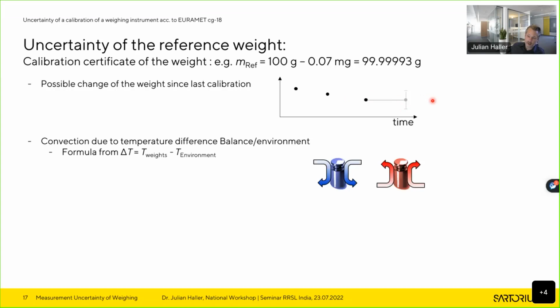And you have to take into account if the weights that you use are not perfectly acclimatized. If you have a temperature difference between the weights and the surroundings, you might get convection. If the weight is colder than the surroundings, then air that approaches the weight will cool down, go downwards and, by friction, cause a force on the weight. So a colder weight will appear heavier, while a warmer weight will appear lighter. And you have to take that into account. This can only be done by a reliable estimation of the temperature of the weights and of the environment. And if you have that temperature difference, again, a formula is given in the CG18 for how you can calculate the respective uncertainty contribution.